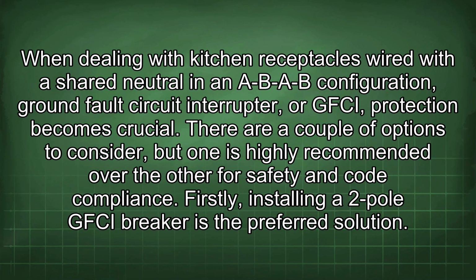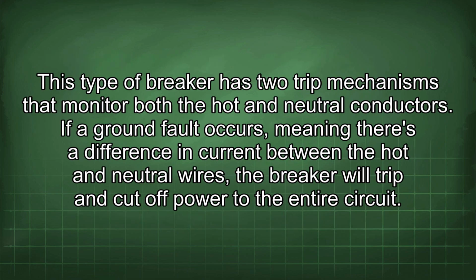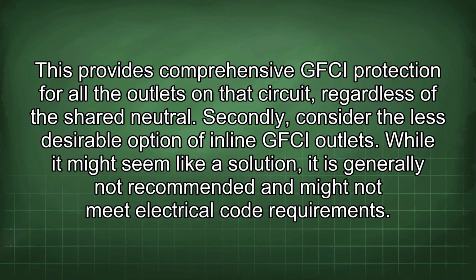When dealing with kitchen receptacles wired with a shared neutral in an A-B-A-B configuration, ground fault circuit interrupter, or GFCI, protection becomes crucial. There are a couple of options to consider, but one is highly recommended over the other for safety and code compliance. Firstly, installing a two-pole GFCI breaker is the preferred solution. This type of breaker has two trip mechanisms that monitor both the hot and neutral conductors. If a ground fault occurs, meaning there's a difference in current between the hot and neutral wires, the breaker will trip and cut off power to the entire circuit. This provides comprehensive GFCI protection for all the outlets on that circuit, regardless of the shared neutral.